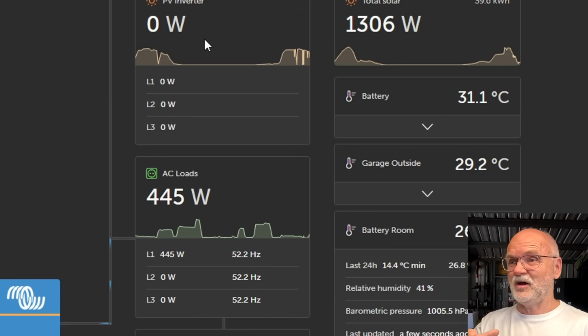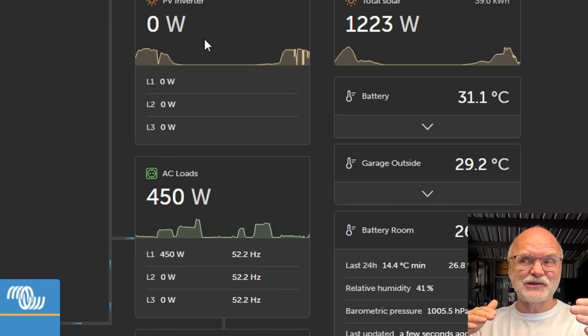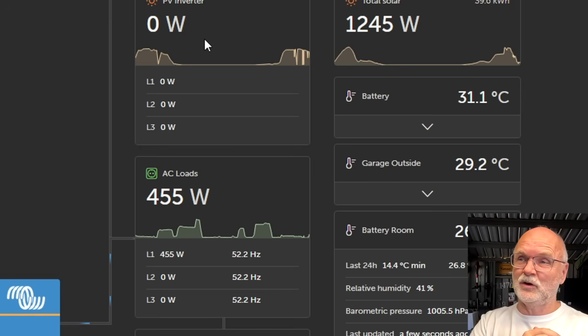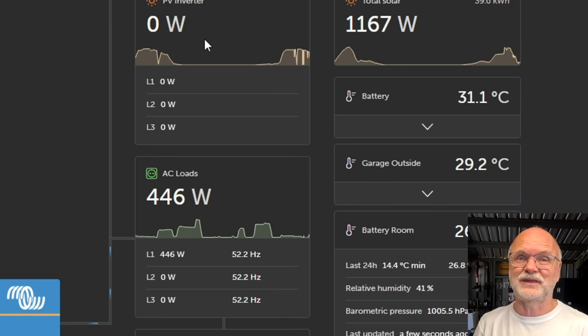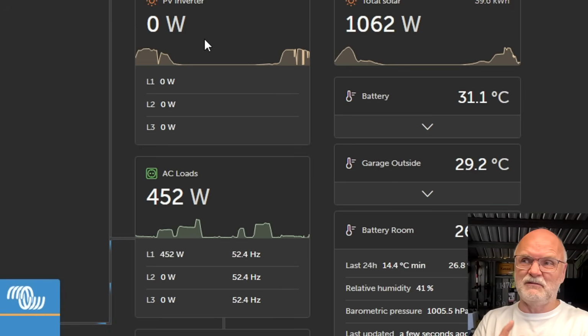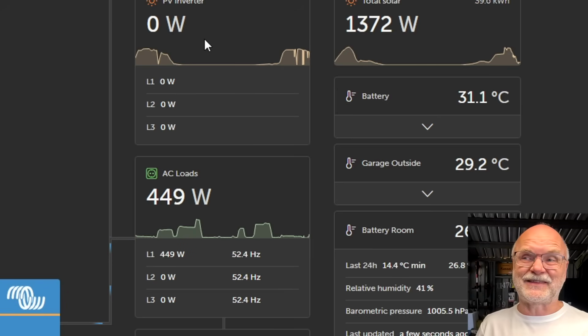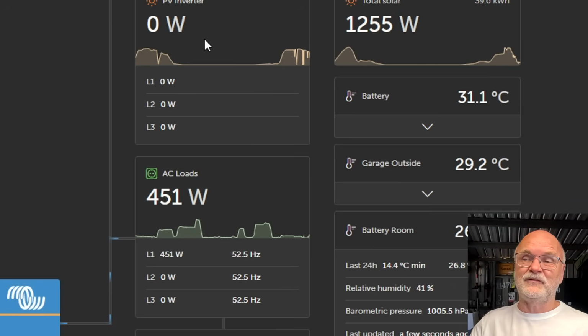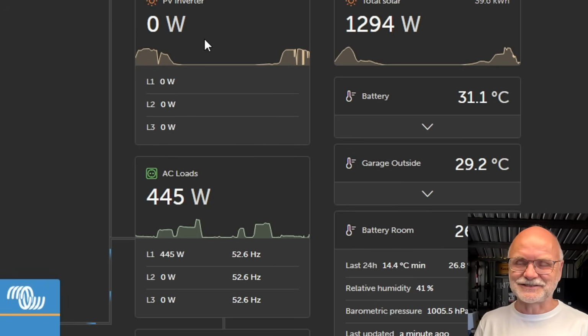This may take, depending on the load, discharging the battery a bit to 53.6 volts may take another half an hour, and then slowly the frequency will go down to 50 Hertz again, and then the tilt system kicks back in to supply whatever additional power we need from this system to hold our 53.6 volts with the batteries and supply power to the load. Obviously at sunset we'll start discharging the battery again, but it will hold at 53.6 volts until then. So amazing how this all works, right?